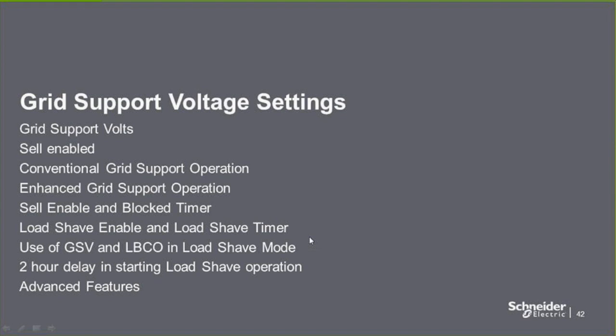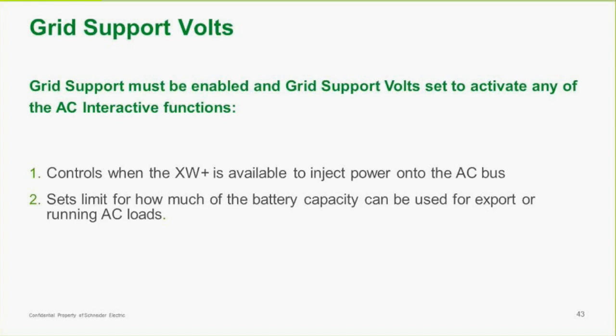So let's talk a bit about grid support voltage settings. Grid support voltage controls when the XW Plus is available to inject power onto the AC bus. This is basically a battery voltage setting, and it limits how much battery capacity can be used for export or for running AC loads.